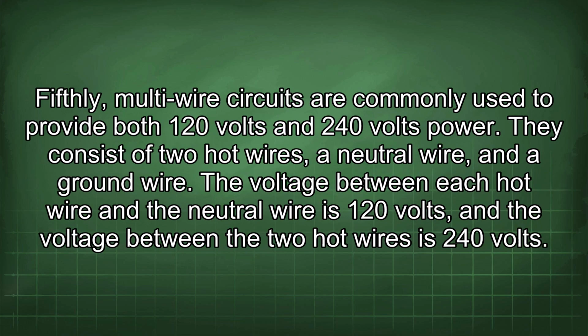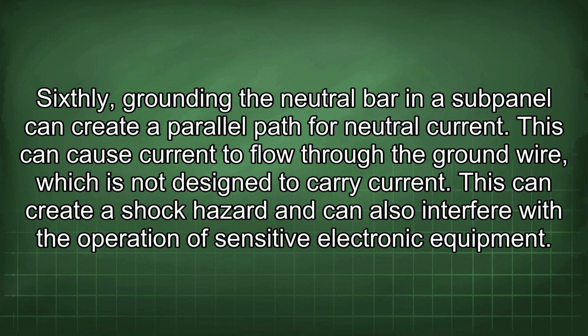Fifthly, multi-wire circuits are commonly used to provide both 120 volts and 240 volts power. They consist of two hot wires, a neutral wire, and a ground wire. The voltage between each hot wire and the neutral wire is 120 volts, and the voltage between the two hot wires is 240 volts. Sixthly, grounding the neutral bar in a subpanel can create a parallel path for neutral current.